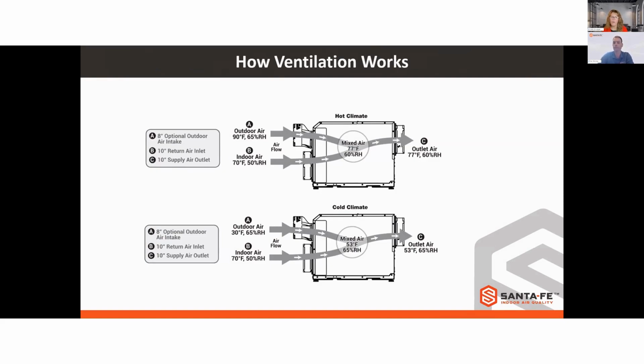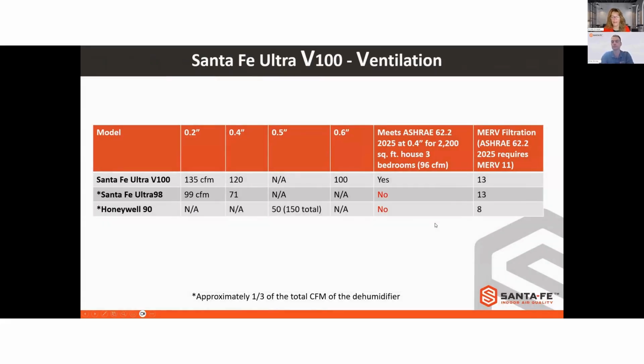Sure. And traditionally in the past, we had said you could bring in with our 6-inch duct approximately 1/3 of the total CFM. Now we're closer to 40%, correct? Yeah. If you look at the cross-sectional area of each of the 8-inch versus the 10, it's much more of the percentages now with that fresh air, if you're wide open on your power damper or whatever damper you do, yep. Great, thank you.